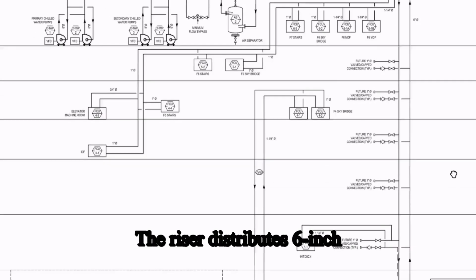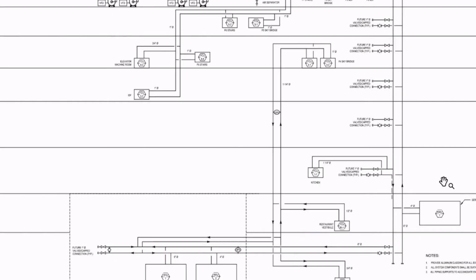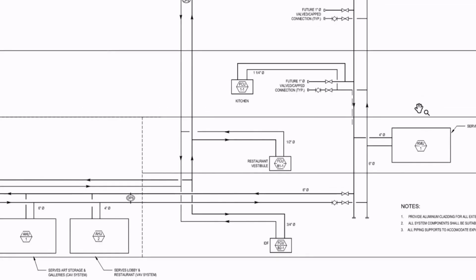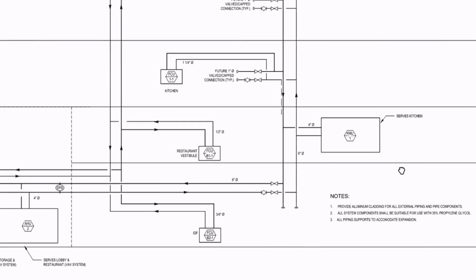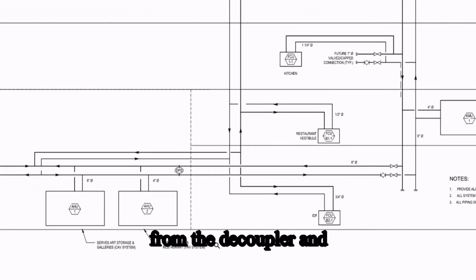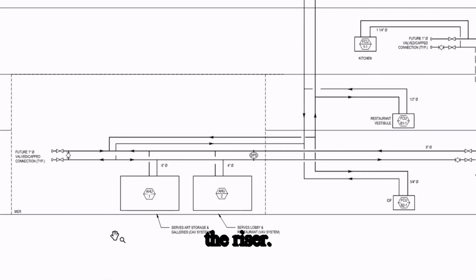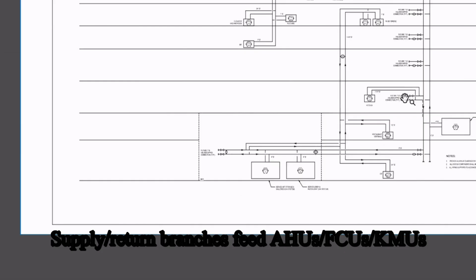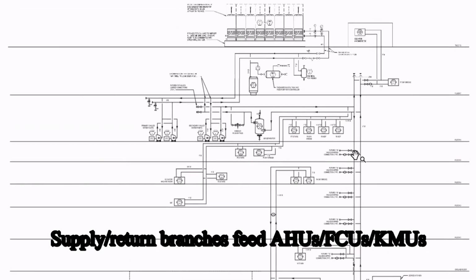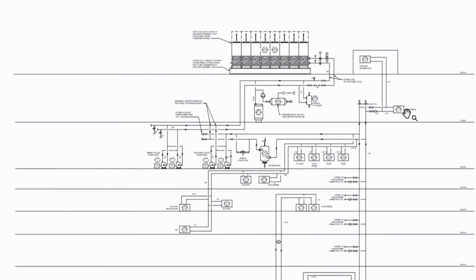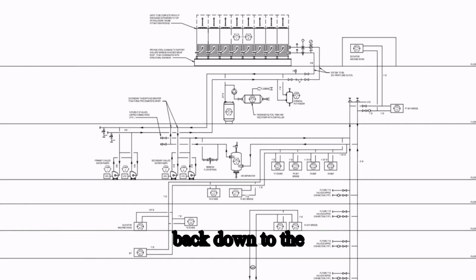The riser distributes 6-inch supply and return lines vertically from the cellar up to the roof, with branches at each floor. Secondary pumps pick up from the decoupler and push chilled water up the riser. Supply and return branches feed AHUs, FCUs, KMUs on each floor. The return riser carries water back down to the chiller plant.